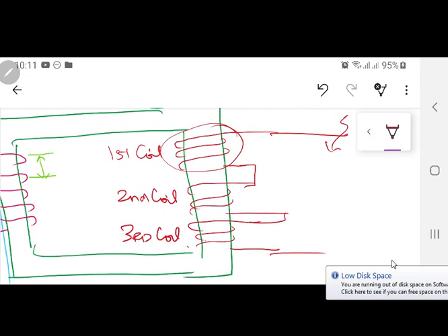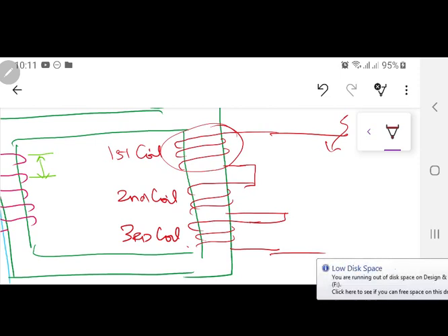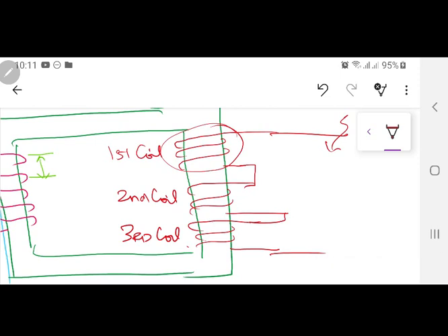Okay. Now in a distribution transformer this problem is not that severe. Okay. So we can have, supposedly, whatever number of turns you take out, you bifurcate into 3 or 4 or 5 or 6 different coils. Now you are already aware that there are taps on a transformer, and those taps are always provided on the high voltage side. So tell me why? The current is small and it's easy to actually have a tap changer over there if it is an online tap changer. Okay. An online tap changer, on load tap changer, is called OLTC.